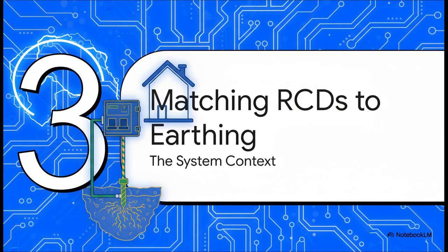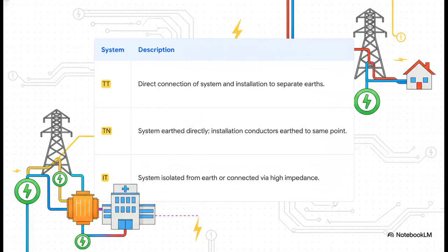But the RCD isn't an island. It doesn't work all by itself. To choose the right one, you first have to understand the very foundation of the building's electrical system, its earthing system. All right, so the IEC 60364 standard lays out three main systems you're going to come across. You've got the TT system, where the supply and the building have their own separate connections to Earth. Then there's the TN system, where they share a common Earth connection. And finally, the IT system, which we'll usually see in critical places like hospitals, where the supply is actually kept separate from the Earth on purpose.